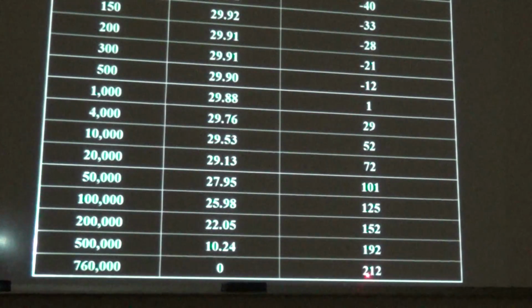What we do is we start at the bottom. Water, when we're at sea level, boils at 14.7 pounds per square inch and will boil at 212 degrees Fahrenheit. So, when we're showing 0 inches of mercury, that means water is going to boil off at 212 degrees. That's 0 mercury. That's the equivalent of 760,000 microns. And if we had PSI, it would be right here, 14.7.